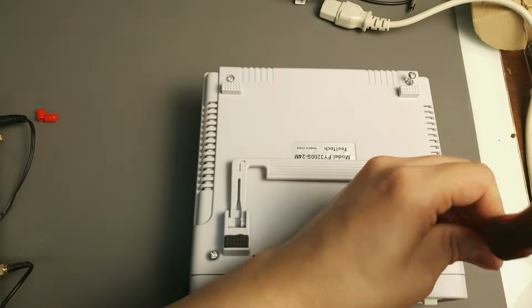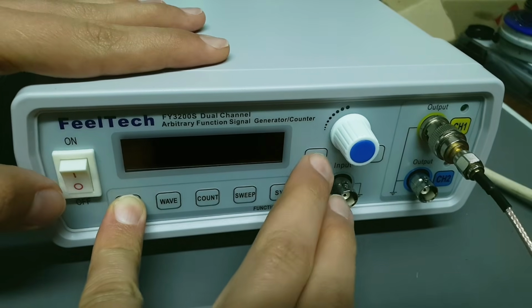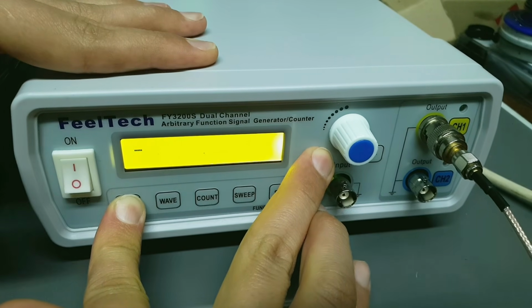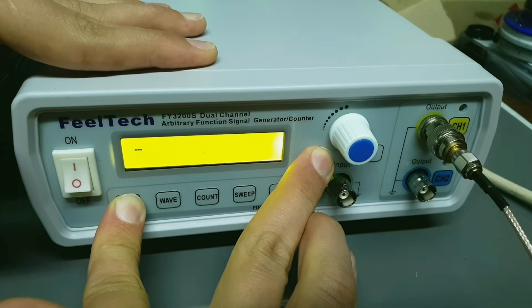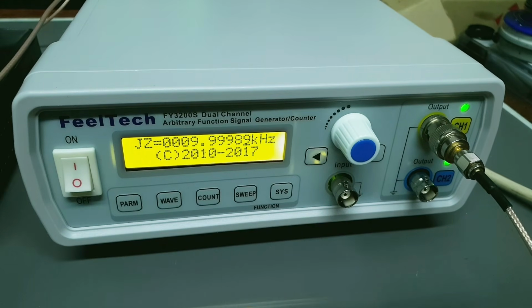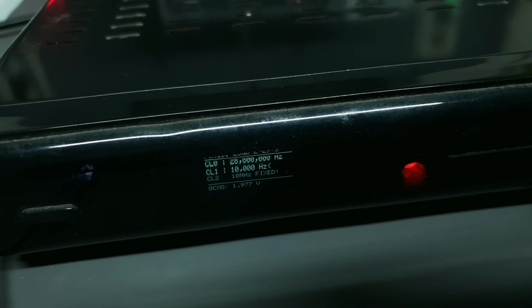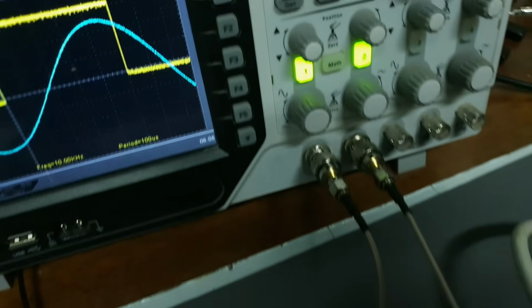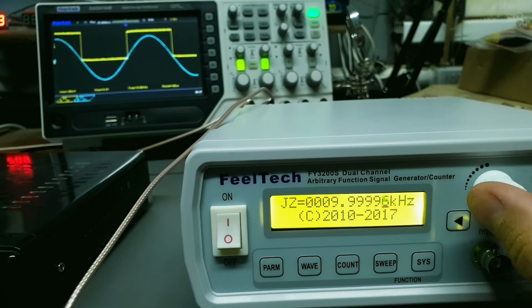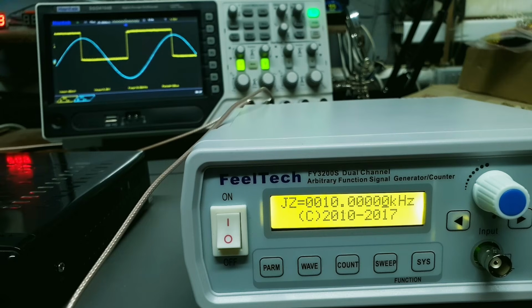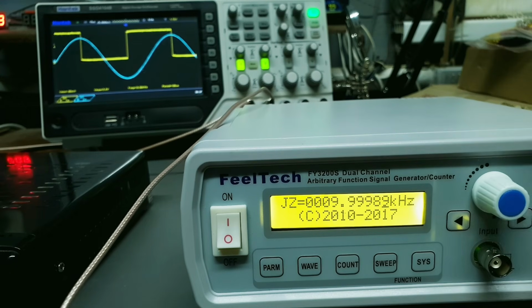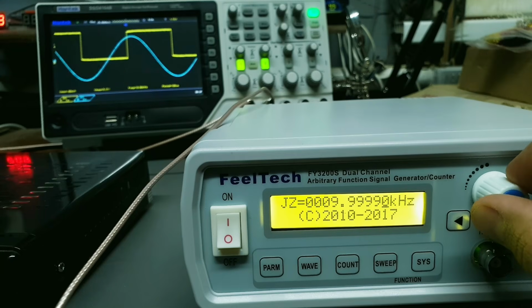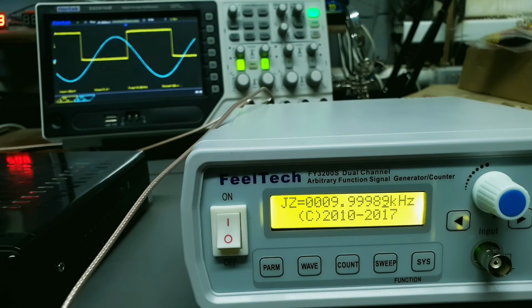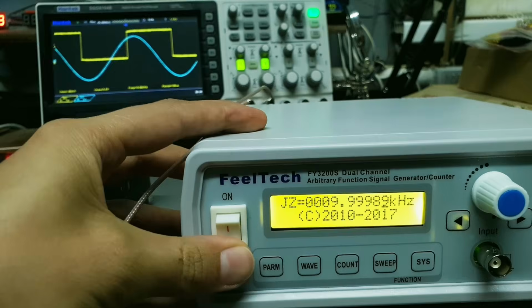Before running the full test, I want to show you how to calibrate the generator's frequency. Hold down the parameter button together with the left button while powering on. The device will output a 10 kHz signal. To calibrate, compare this output with a known reference. In my case, I'm using a DIY GPSDO. With both the signal generator and GPSDO connected to the oscilloscope, you can observe phase drift, because the generator isn't exactly at 10 kHz. Adjust it until there is no drift, or as little drift as possible. Then power off and the calibration is stored.